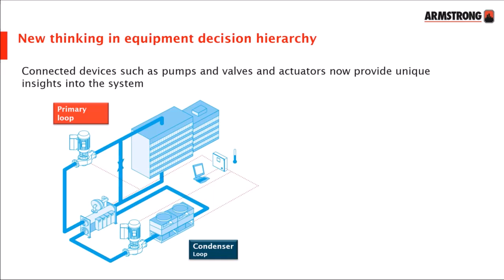Alternatively, if condenser pumps are working harder than they were, say, 3 months ago, to deliver the same flow they were delivering 3 months ago, there may be an issue with the pump, but it's more likely that there's a partial obstruction in the system. Say the towers need cleaning, something like that. And all of that could be picked up through the pump.